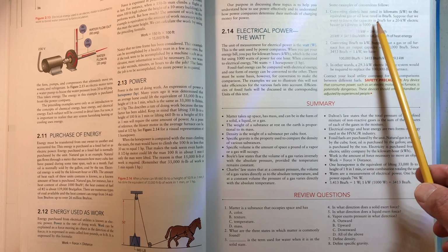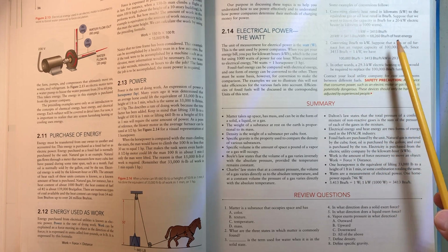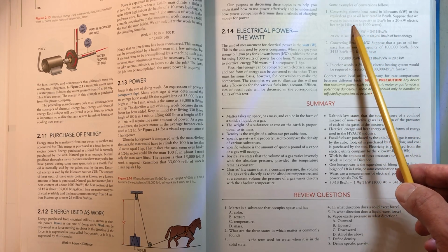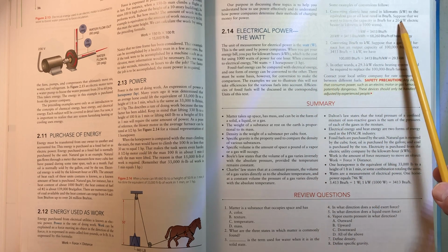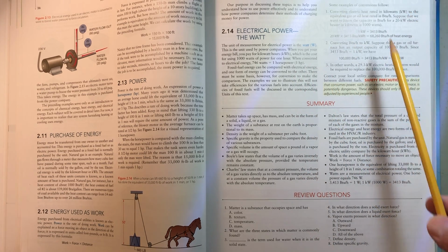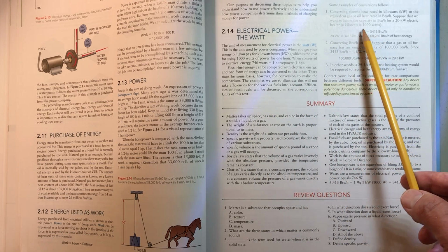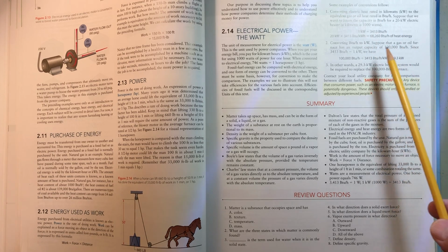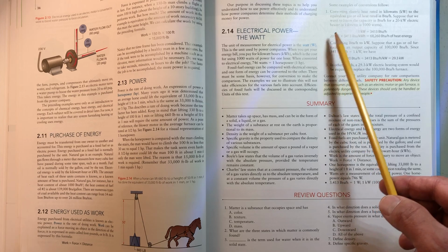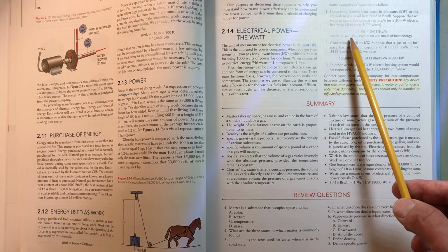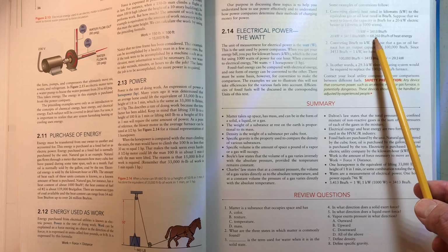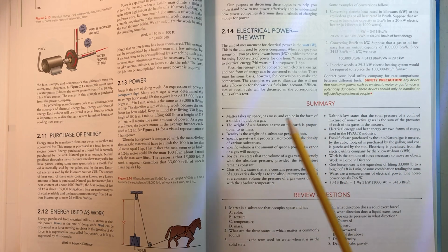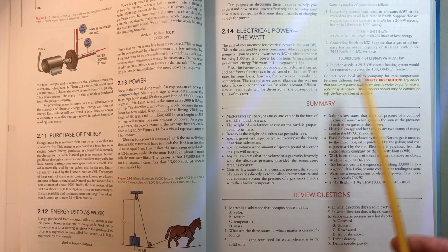So suppose we want to know the capacity in BTUs per hour for a 20 kilowatt electric heater, and we're going to replace it with a gas furnace. We know that a kilowatt is 1,000 watts, so we're looking at 20,000 watts of electric heat. If we know that 1,000 watts, or 1 kilowatt, is equal to 3,413 BTUs per hour, we can multiply our 20,000 watts by 3,413 BTUs, and we get 68,260 BTUs of heat energy needed to match that 20 kilowatt electric heater.